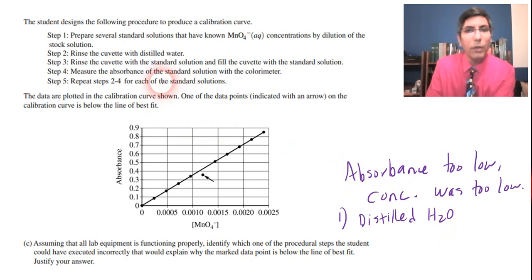water that got into the cuvette that didn't get completely cleaned out. And so this is perhaps a fault in step three, that they didn't really rinse the cuvette with the standard solution as they were supposed to. And they just left the, that distilled water in there.